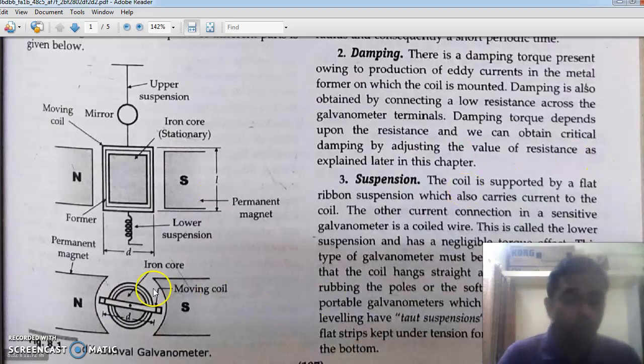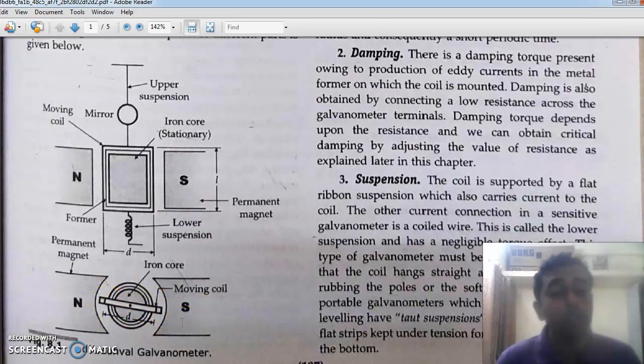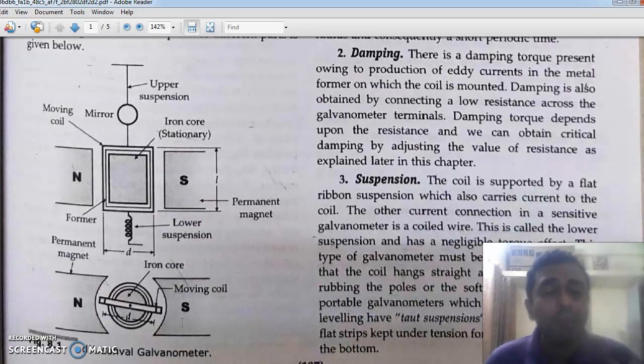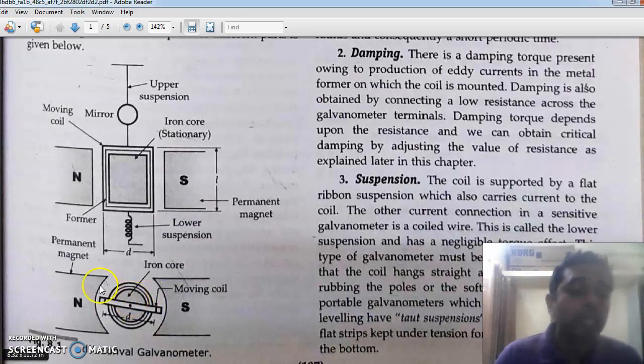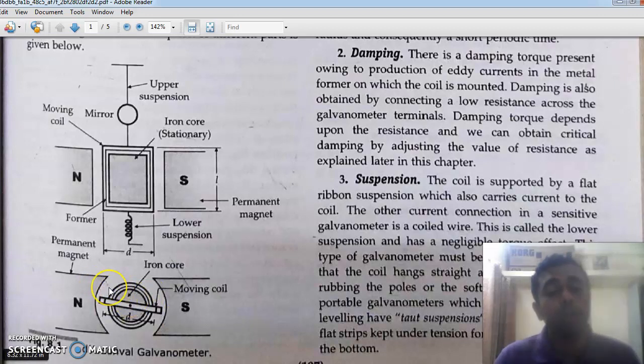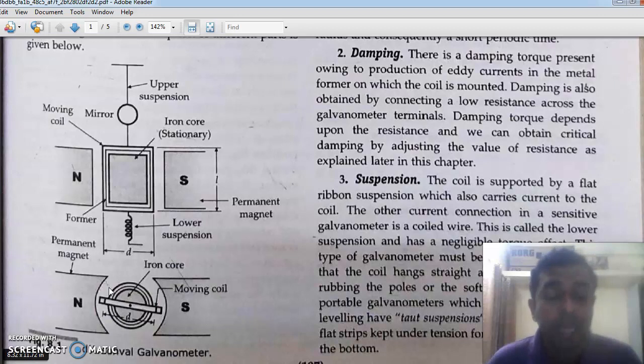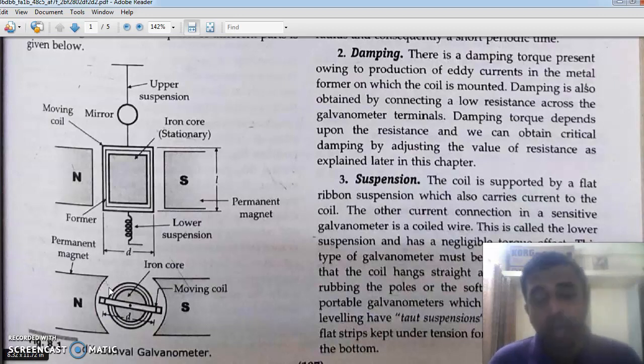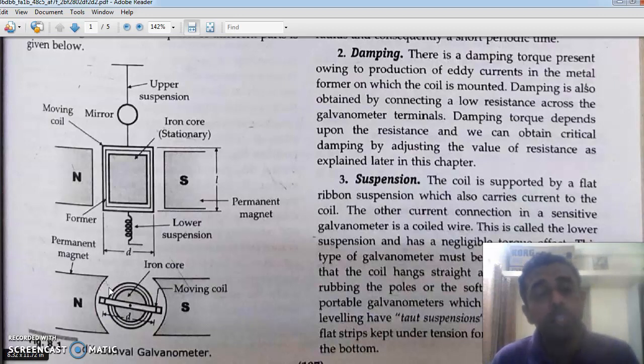In the top view, you can see that these magnets are horseshoe magnets. Why horseshoe magnets? They create a uniform radial magnetic field. The importance of the radial magnetic field is that the coil and the field lines will always be orthogonal — that is, 90 degrees — at every point. This radial magnetic field, created by a pair of horseshoe magnets, will allow maximum torque to be generated.